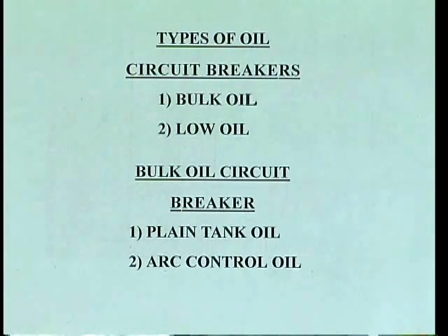One is it acts as an arc quenching medium. The second is it provides insulation between the line conductors and earthed components, whereas in low oil circuit breakers, where minimum oil is used, this minimum oil is only used for extinction of the arc, but the electrical conductors are insulated by air or porcelain or some other inorganic insulating material.